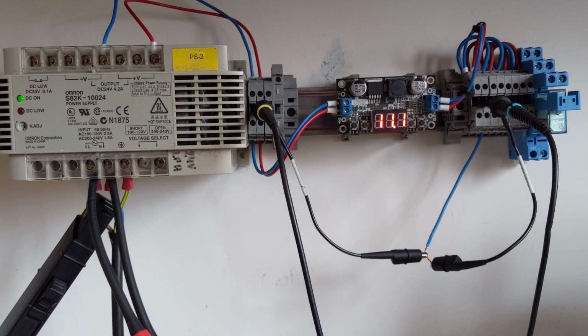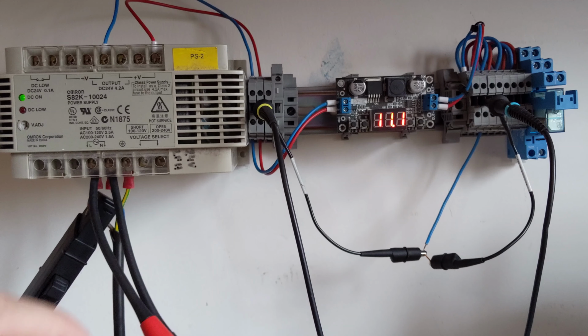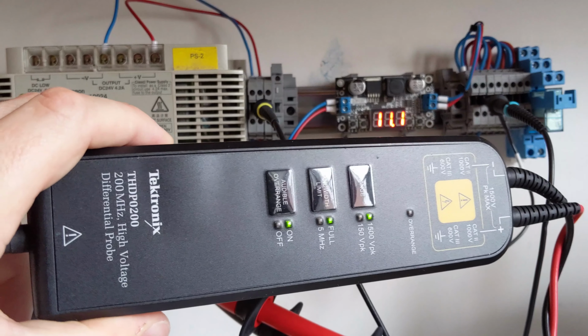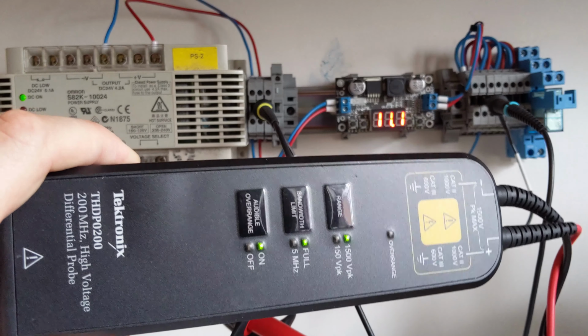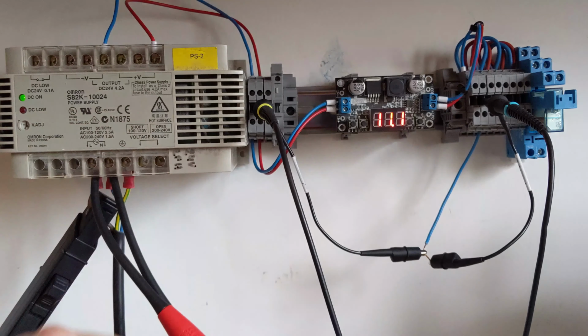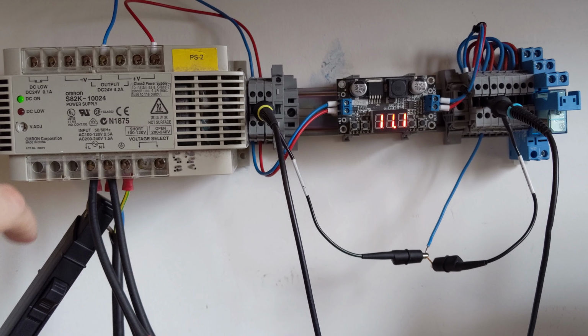So to do a current input harmonics measurement, generally you want to probe the voltage of the AC line. So I've got a THDP0200 high voltage differential probe here. Typically you'd use something like this to take this measurement.